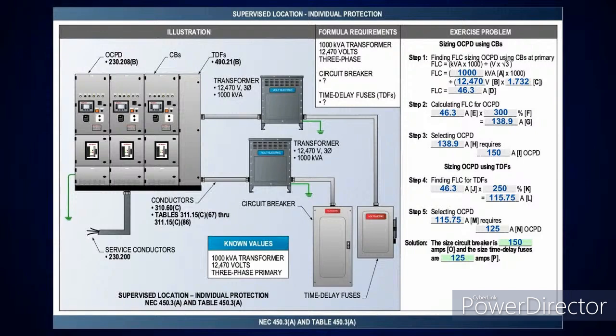Just like when we started this at the very first, if you have something in kVA, you take it times 1,000 to put it in VA form, then take whatever the voltage is and divide it into the VA of the transformer. In this case, it'd be 46.3 amps. And if I'm sizing the circuit breaker, as we just discussed, you're going to take that at 300%.